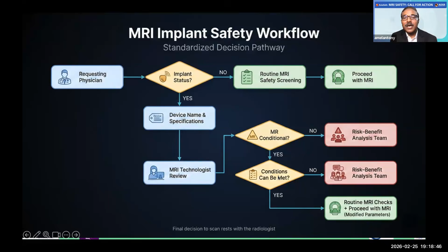Conditions can be met, or they cannot be met; again, risk-benefit analysis. And if conditions can be met, one can go ahead with this. The two most important things we come across are cardiac pacemakers and DBS. For cardiac pacemakers, we know that now we have pacemakers which are even compatible with 3 Tesla. The most important thing is that an electrophysiology technologist or an electrophysiology-trained cardiologist should be available to reset the pacemaker before and after the scan.